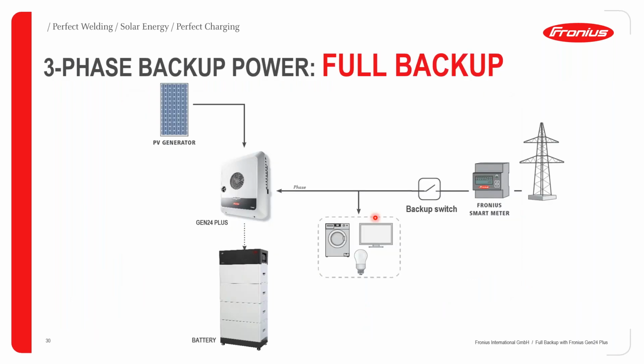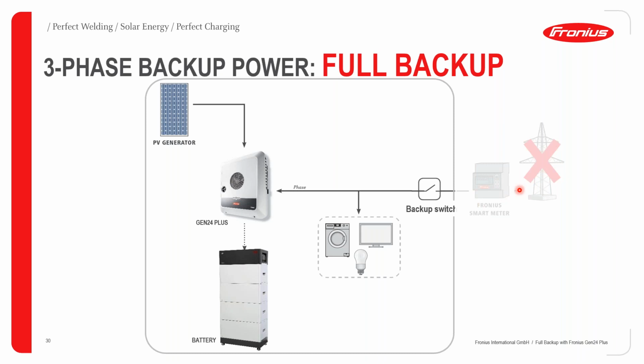Going on, we now have an SLD, single line diagram, of how this looks in full backup mode. Basically, when there's a grid outage, there will be no longer supply from the grid, and most importantly, this backup switch swings into play because it will have to disconnect the connection between the AC bus bar, the connection between the inverter and the grid, so as to allow the inverter to build up its grid and then supply load from the battery, as we will see in the following illustration.